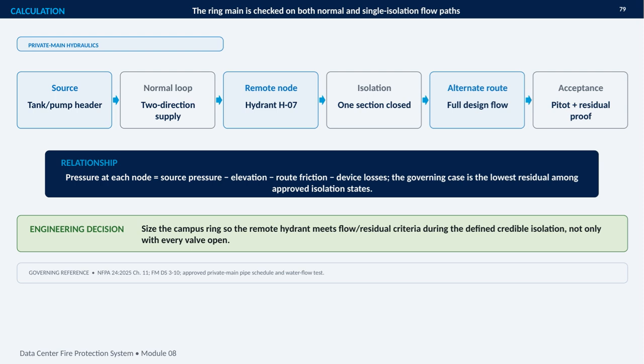Here, the critical point is identified as hydrant H07. Acceptance is then demonstrated through the required flow and residual pressure proof, using pitot measurements and residual readings. The governing references are NFPA 24, 2025 edition, Chapter 11, FM Data Sheet 3-10, the approved private main pipe schedule, and the water flow test.